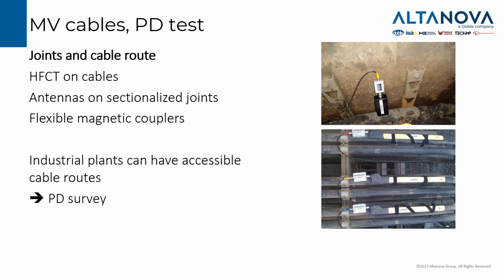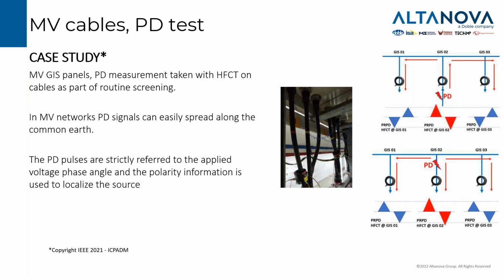When we have instead accessible joints or accessible cable routes, we can use UHF antennas to test the spliced joints directly, so we can place the antenna directly over the joint, or we can place a flexible magnetic coupler along the cable routes to cover properly all the length of the cable with quite high sensitivity. Here we have a case study.